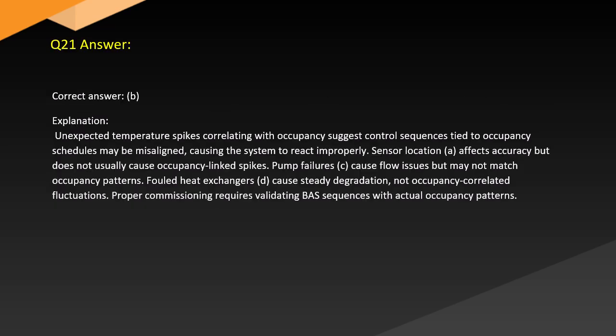Answer. Correct answer. B. Explanation. Unexpected temperature spikes correlating with occupancy suggest control sequences tied to occupancy schedules may be misaligned, causing the system to react improperly. Sensor location affects accuracy but does not usually cause occupancy-linked spikes. Pump failures, C, cause flow issues but may not match occupancy patterns. Fouled heat exchangers, D, cause steady degradation, not occupancy-correlated fluctuations. Proper commissioning requires validating BAS sequences with actual occupancy patterns.